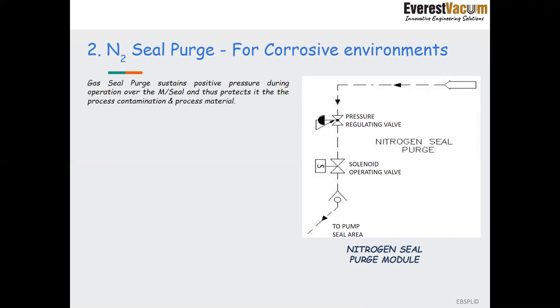So what does this gas seal purge do? It sustains positive pressure during operation of the mechanical seal, and it ensures that the product carryover, the process carryover that comes into the pump, doesn't come into contact with the mechanical seal, and it protects against process contamination and the contamination of oil at the end. So it is very critical: if the process carryover is stopped from entering into the oil chamber, we are enhancing the life of the overall product. The life of the seals, bearings, oil, everything will be under control.